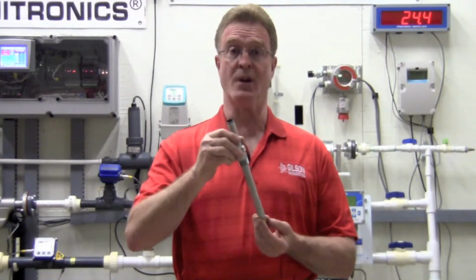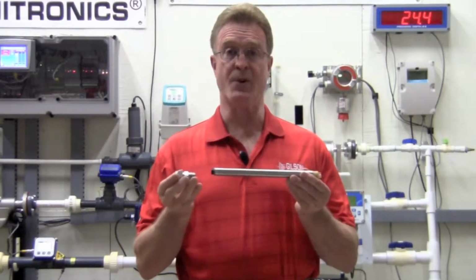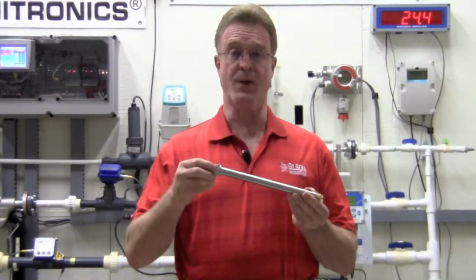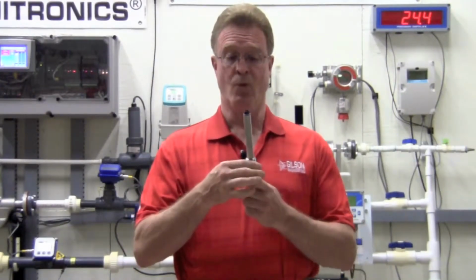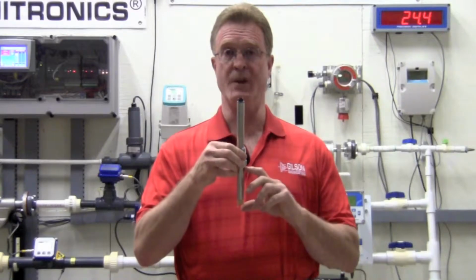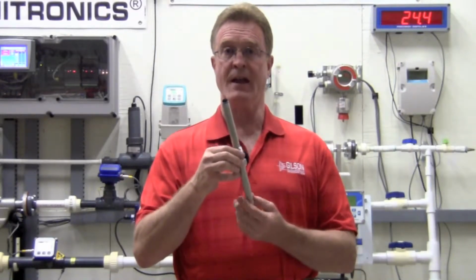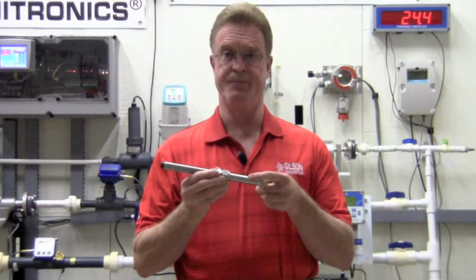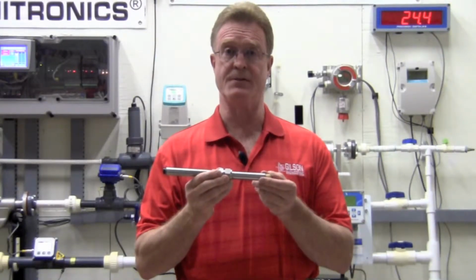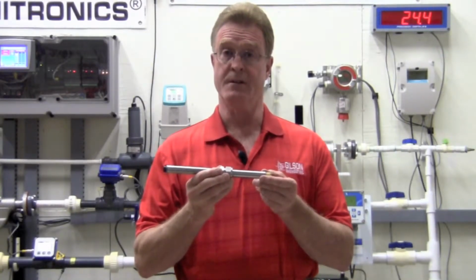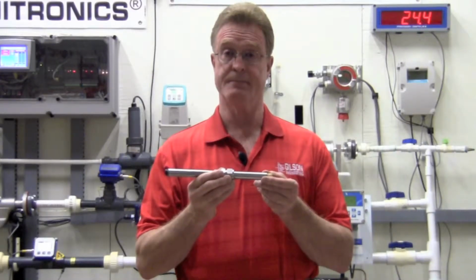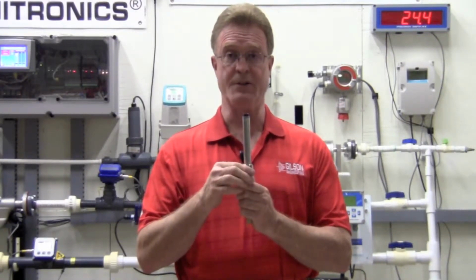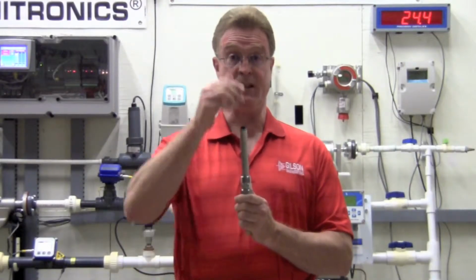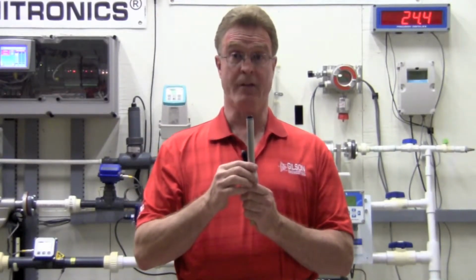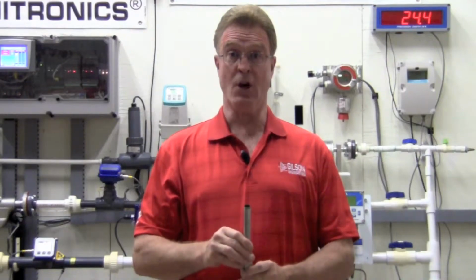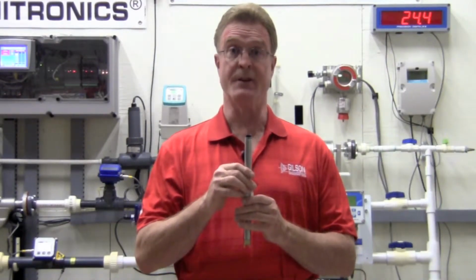In those applications where I have a deeper tank, we can take that compression fitting and reverse it so that the threads face upward. We can position that on the sensor 3 inches up from the bottom, as on the very face of the sensor, internally we have a temperature sensor. Temperature is important to many measurements, including pH. We would then connect the 3/4 inch NPT, fish the leads up through a piece of pipe of a length that would be long enough to lower our S10 sensor so that it is always wetted.